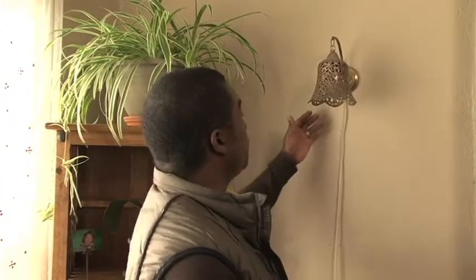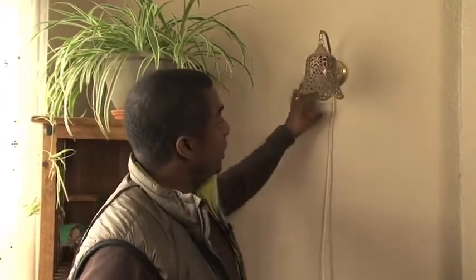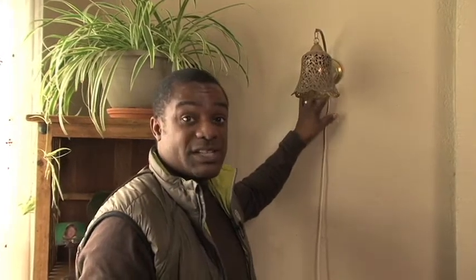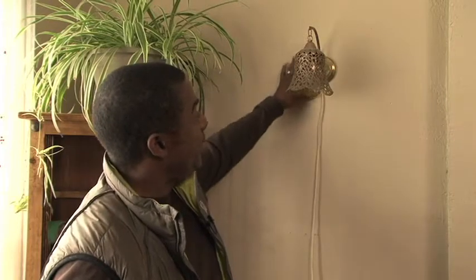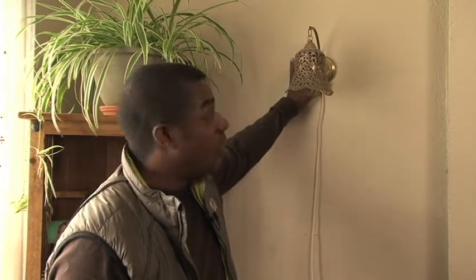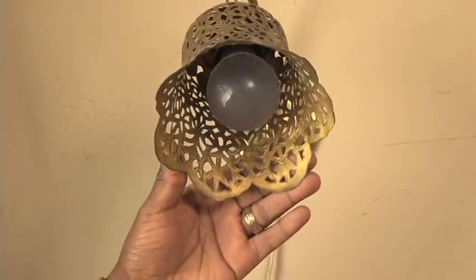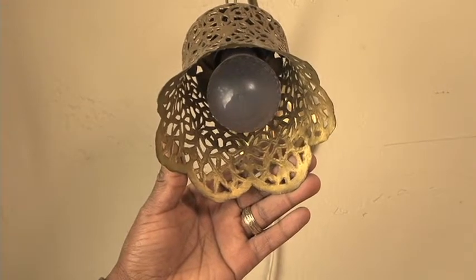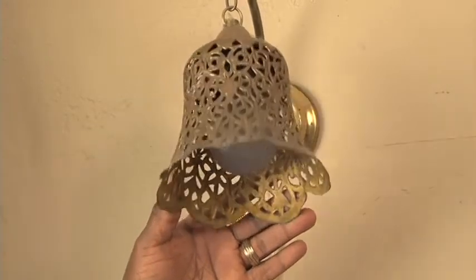The next item of interest we arrive at is this lighting fixture. Now, the two things we want to keep in mind when we're evaluating lighting fixtures are, one, how well does the lighting fixture attach to the surface, the wall or the ceiling that it's attached to, and two, what kind of lamp is in it. For example, this one has a real nice attachment to the wall and it has an incandescent bulb inside. So that could be replaced by a CFL to improve efficiency.